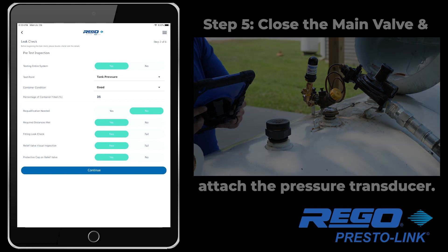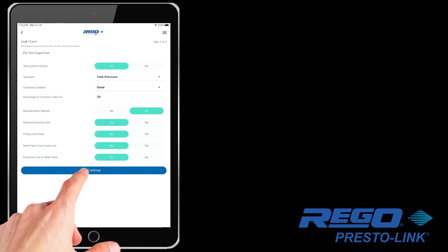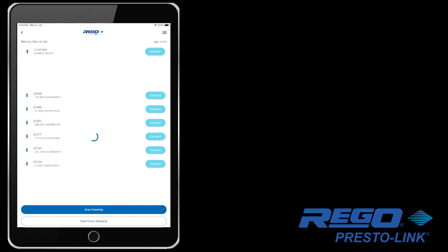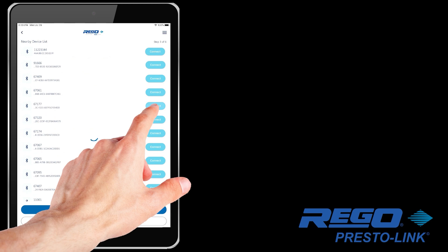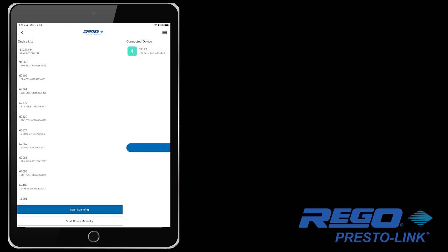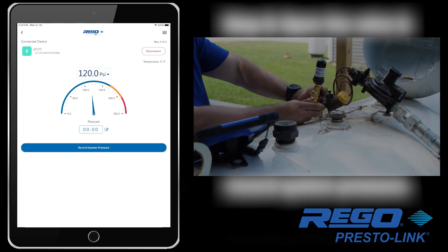Go back to the tablet and click Continue. Then from the list, choose the PrestoLink device that you placed on the tank. In our case, the number on the transducer is 67177. You will see a graphic representing the current pressure, and since you turned the valve off before connecting it, it should be at 0 pounds of pressure.